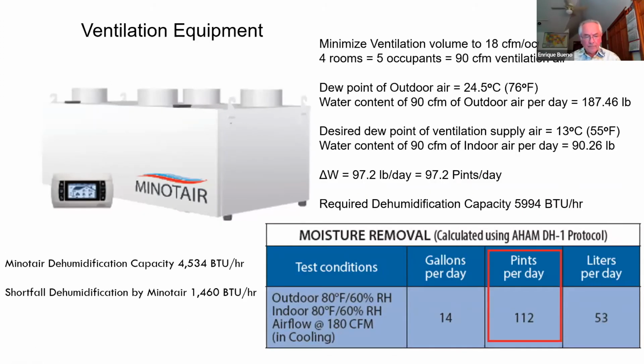In terms of ventilation, ventilation air is the main source of humidity. Therefore, it's necessary to minimize the ventilation volume to the 18 CFM per occupant that Phius recommends or specifies. So 4 rooms equal 5 occupants equal 90 CFM ventilation air. The dew point of outdoor air is 24.5 centigrade, 76 Fahrenheit. So the water content of 90 CFM of outdoor air per day will provide 187.46 pounds of water. So the desired dew point of ventilation supply air is 13 centigrade, 55 Fahrenheit.